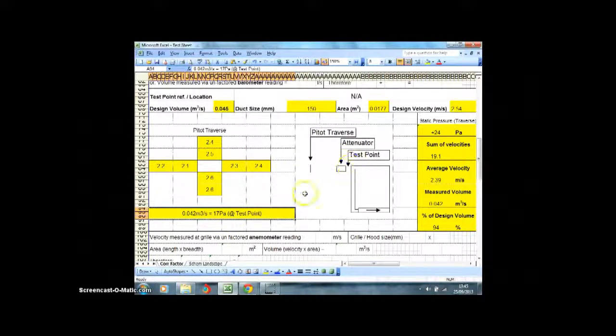And at the test point, I measured 17 pascals. Back at the traverse point, I obtained 24 pascals, but that's not important. It's the 17 pascals at the test point that we're concerned with. That came out to about 94%. As anyone would know, for the correction factor you're looking for somewhere reasonable, between 90 and 110, for instance, which I'd accept.